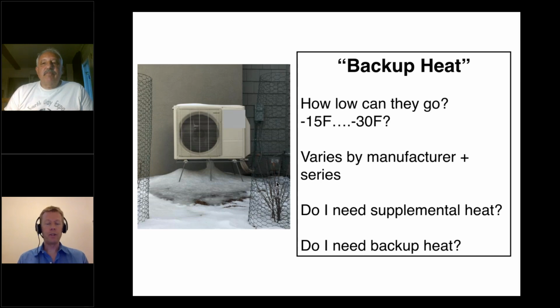Some manufacturers publish their actual cutoff temperature, where the outdoor unit will actually shut down and the air handler keeps going. And then other manufacturers don't actually publish that, so it does vary. So as you do your heat load calculations, you'll need to consider, do you need supplemental electric resistance heat? In some cases with really high performance houses, you might not really need it. And then you get into a conversation with your clients about, what do they want to do for backup? Do they want to have electric resistance backup heat that's integrated into the air handler? Some clients just prefer to have an electric fireplace, or they put a couple of electric space heaters in a closet and pull them out if there is a mechanical problem with their heat pump.